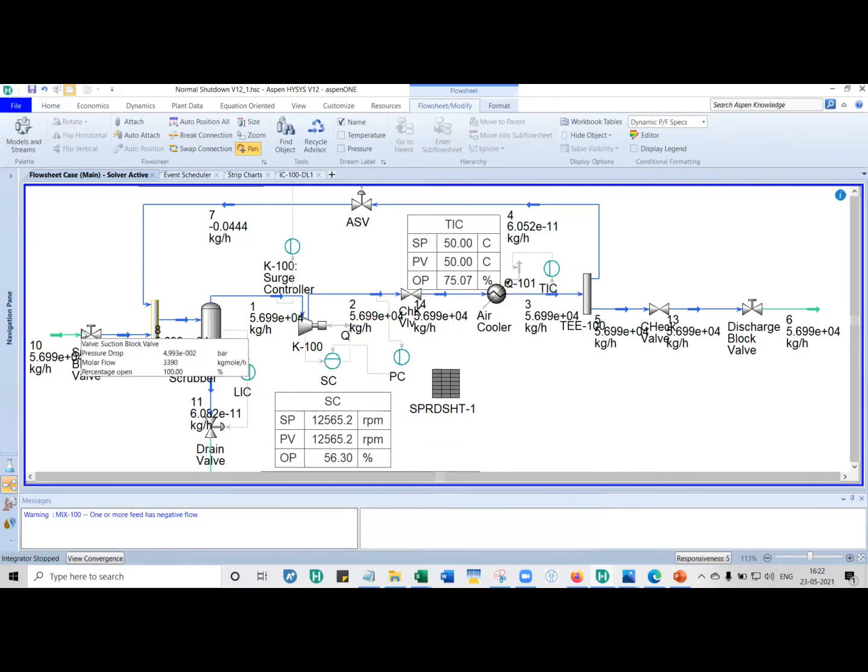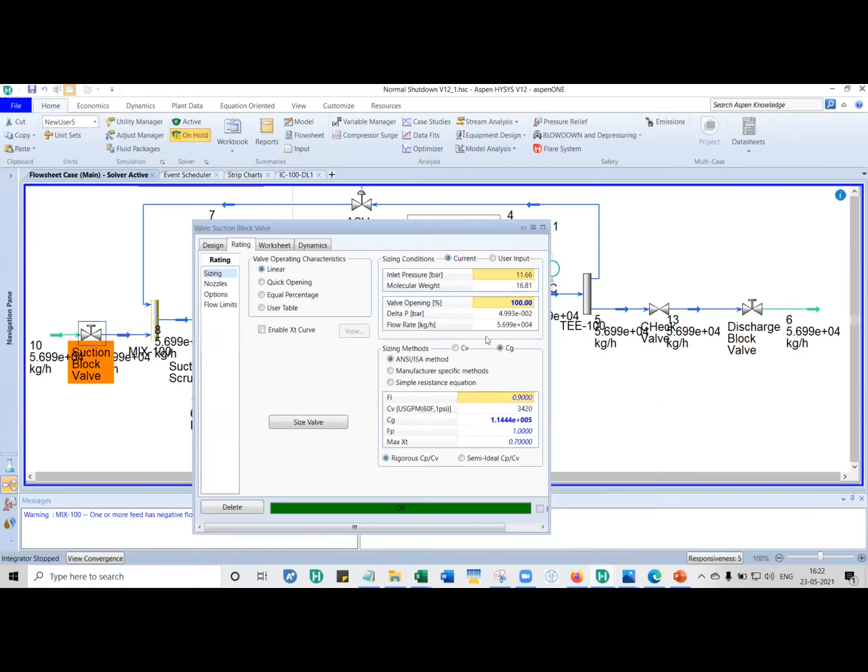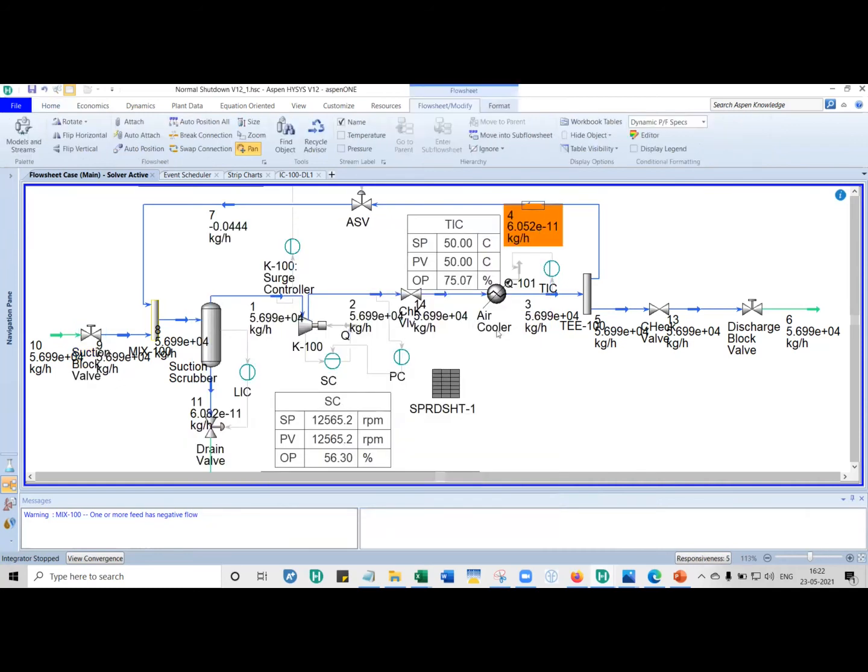and block valves also, both check valves and block valves give a high CV value. By giving a high CV value, because you see, if they're all full bore valves, if you look into the pipe, so you have a pipe and you have a valve, if it is open and you look through it, the valve's opening is the same as the pipe's opening. So in such cases, you can give a high CV to say that there is hardly any pressure drop across the pipe. So check valves and block valves, you just approximate it to almost no pressure drop.